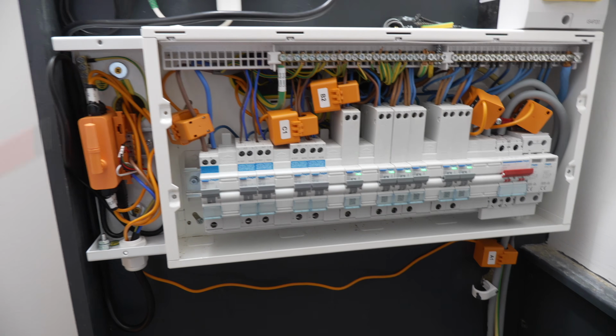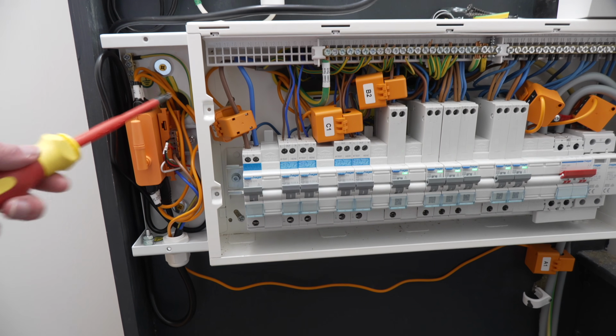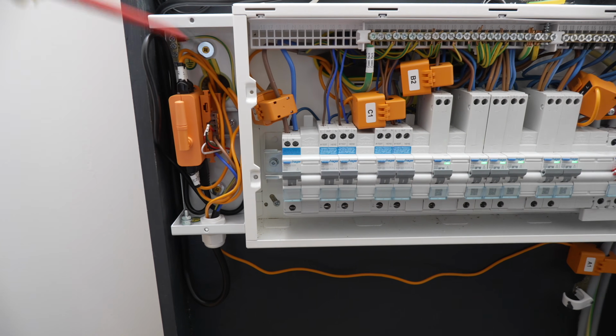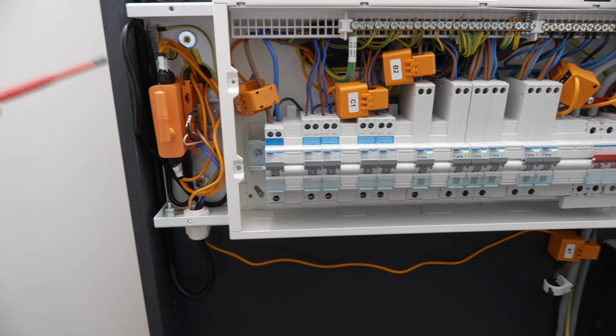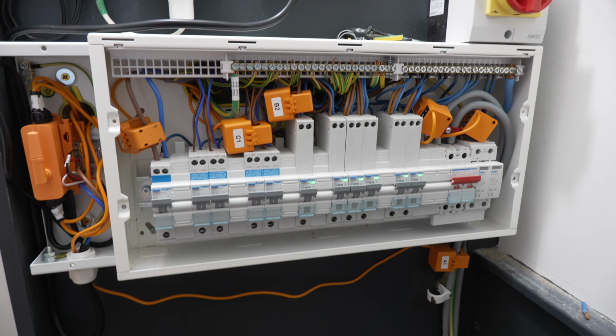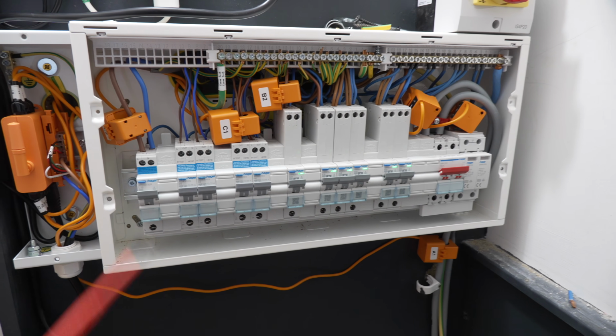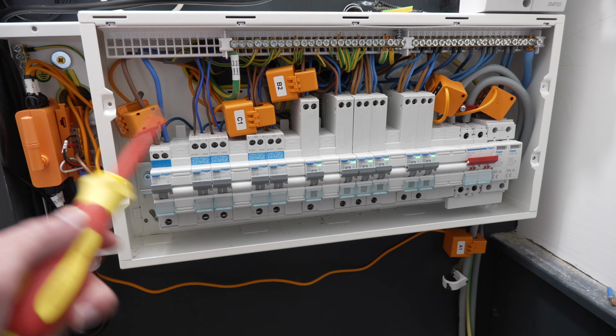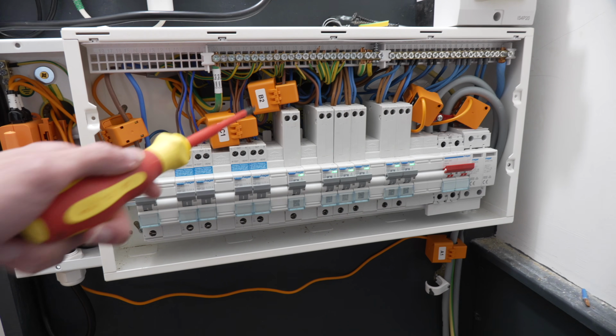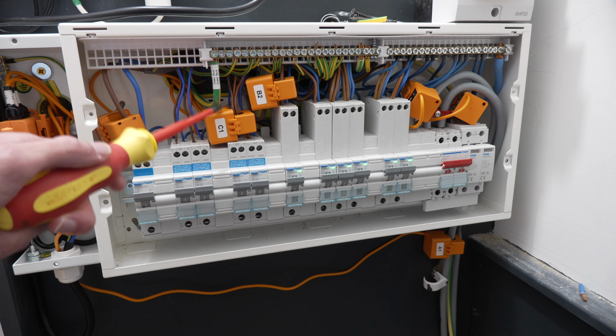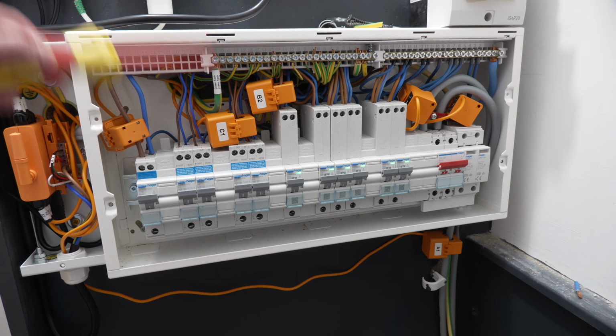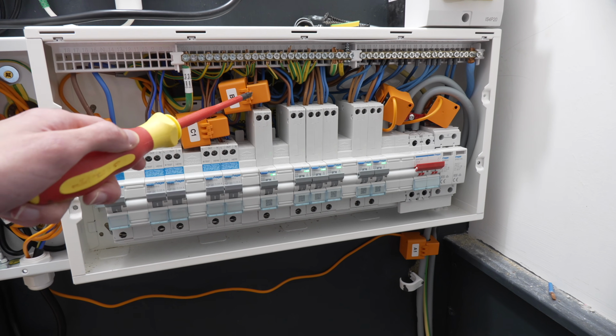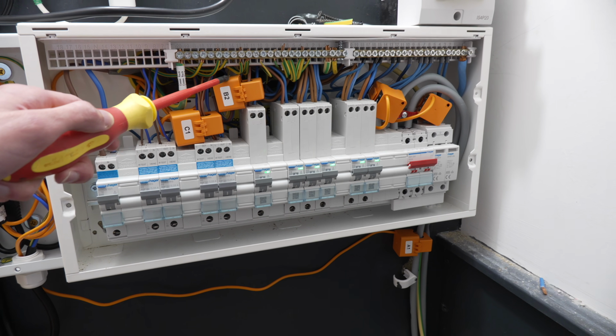So on the left here, we have the energy monitor installed in its enclosure. The CT cables then go through that hole in the wall, and most of the slack is stashed behind this board here. There's a bit of slack looped around inside here. Then for power, the cable comes out of here and goes up, and it's plugged into this socket up here. And then inside the board, we can see all the CTs. So we have one CT around the line conductor for the solar, one CT around the line conductor for the 3 different lighting cables going out, so that's 2 different lighting circuits, and one of them has 2 cables in it. This CT is around the line conductor for my comms rack circuit.